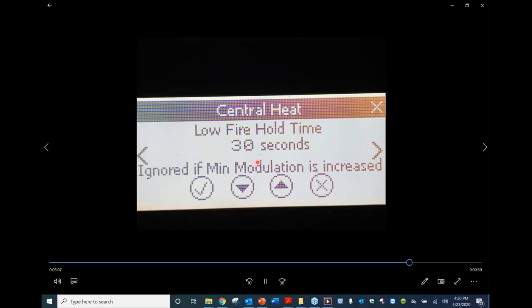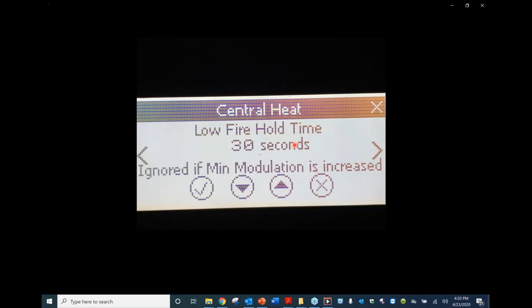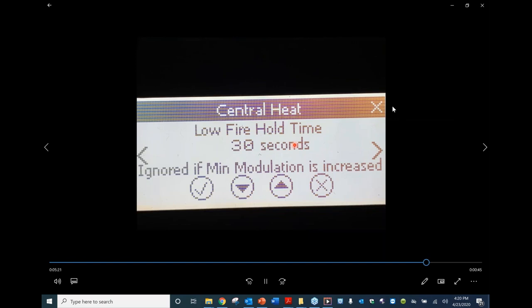So this is adjustable from 0 to 3 minutes. And we can adjust that, and it'll hold the boiler in this lowest firing rate to see what's going on. As soon as it's done, it will release and go to where it needs to be.